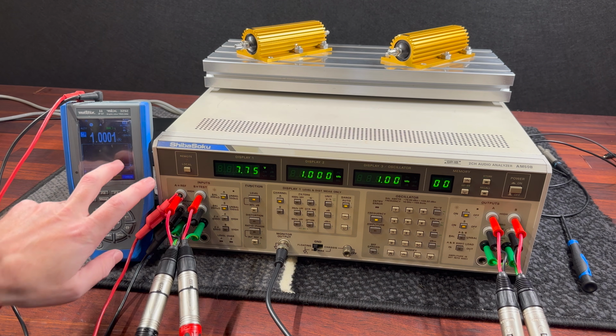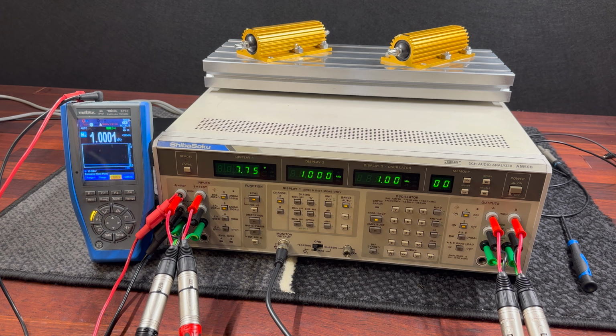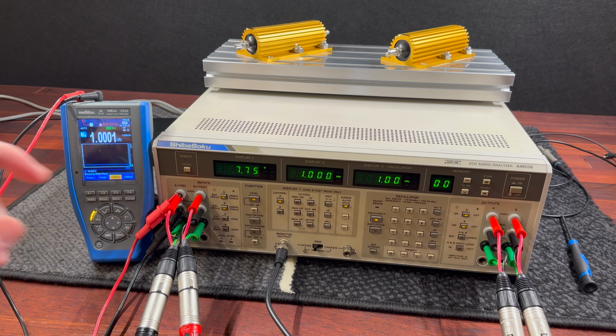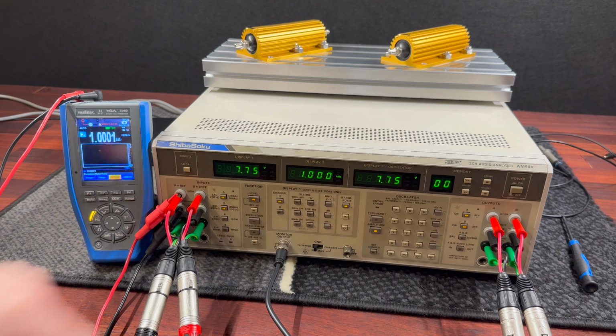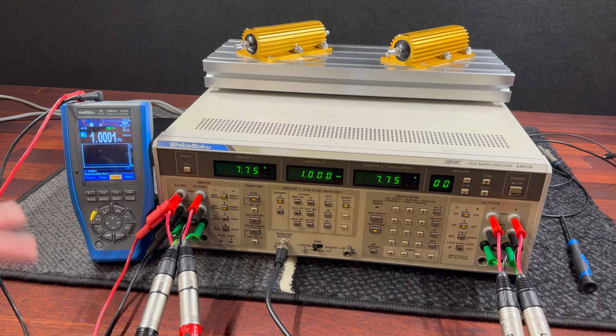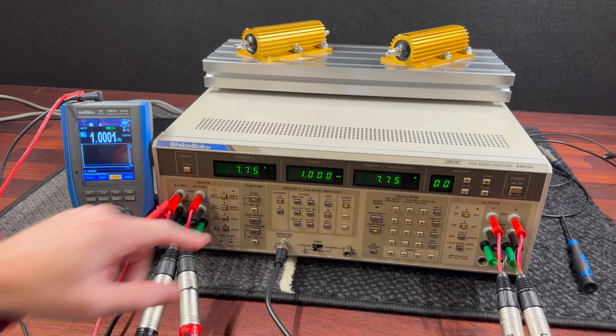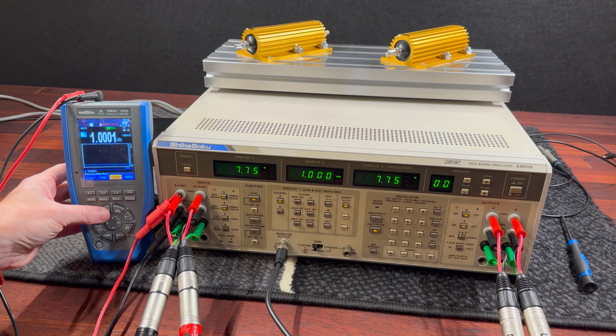So I ended up using my multimeter, which does have frequency and voltage measurements, and there are trim pots in the oscillator section that we can tweak. There's a trim pot for oscillator level, which allows us to adjust the amplitude, which is currently 7.75 volts, and we are reading 7.75 volts. This is not what it was reading originally. It was quite out of whack.